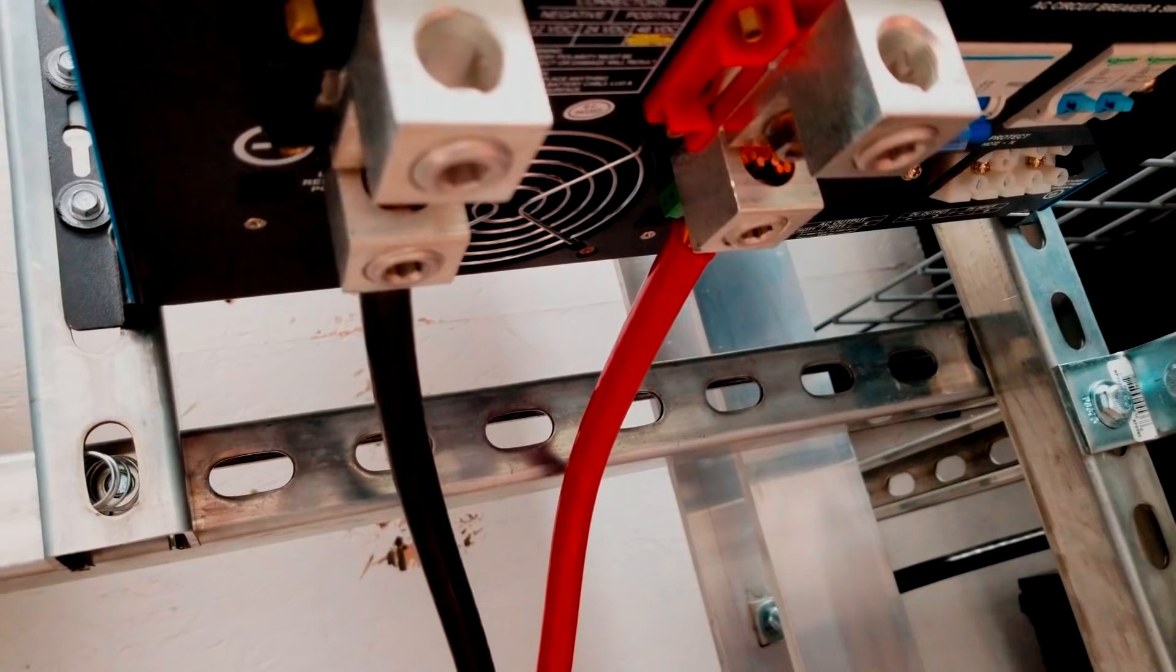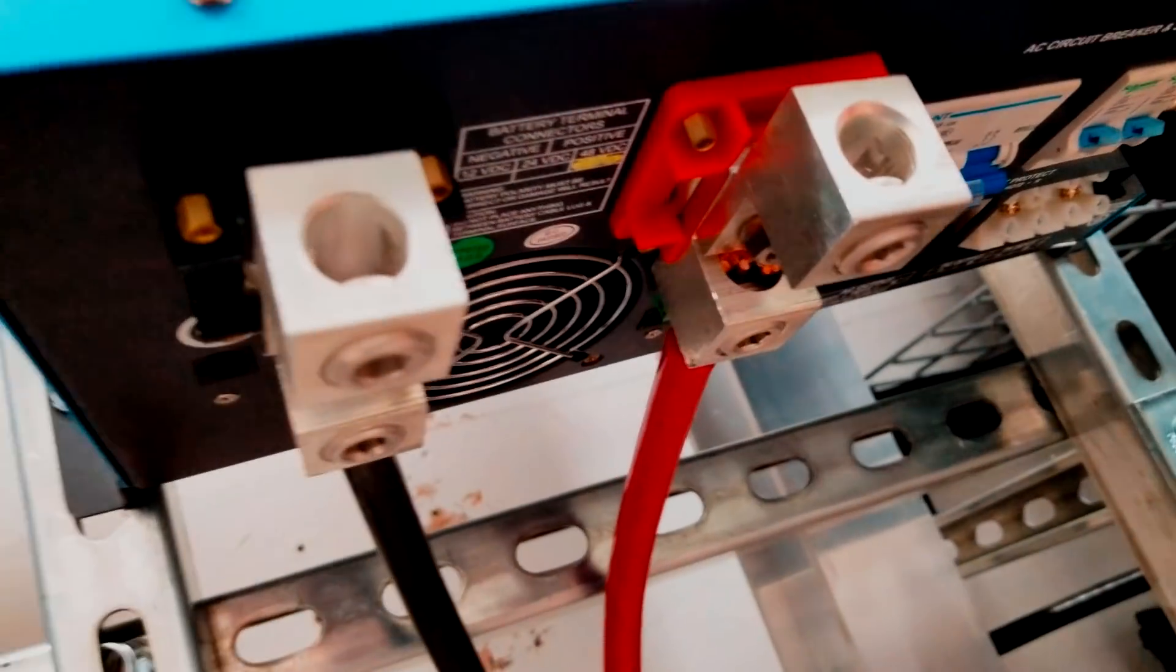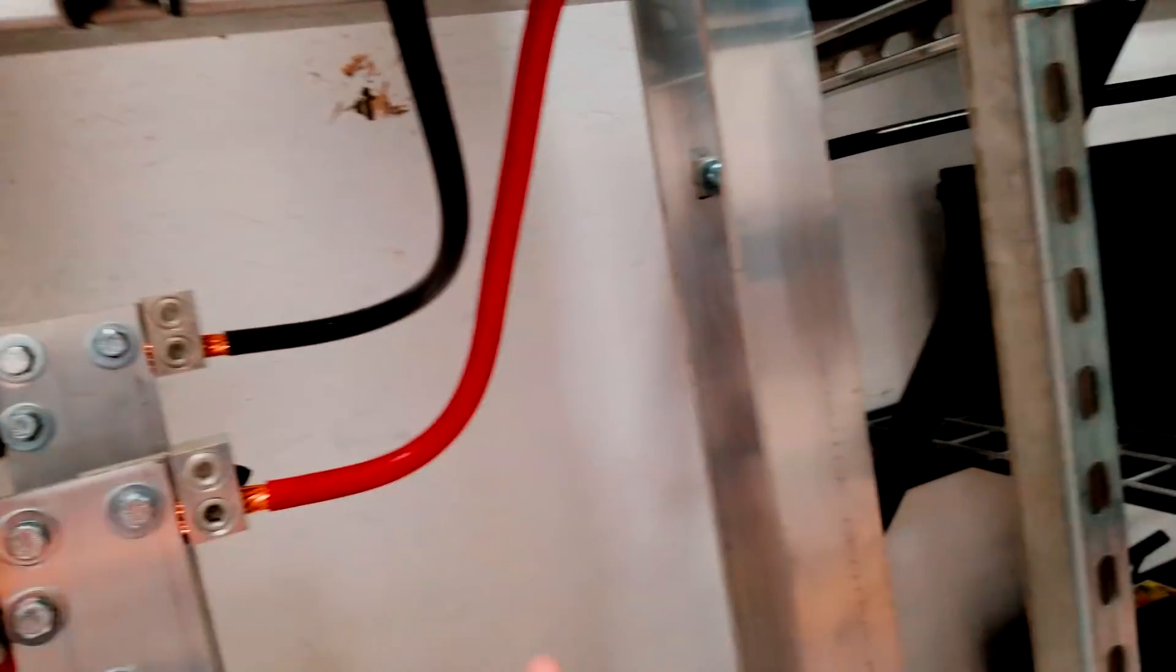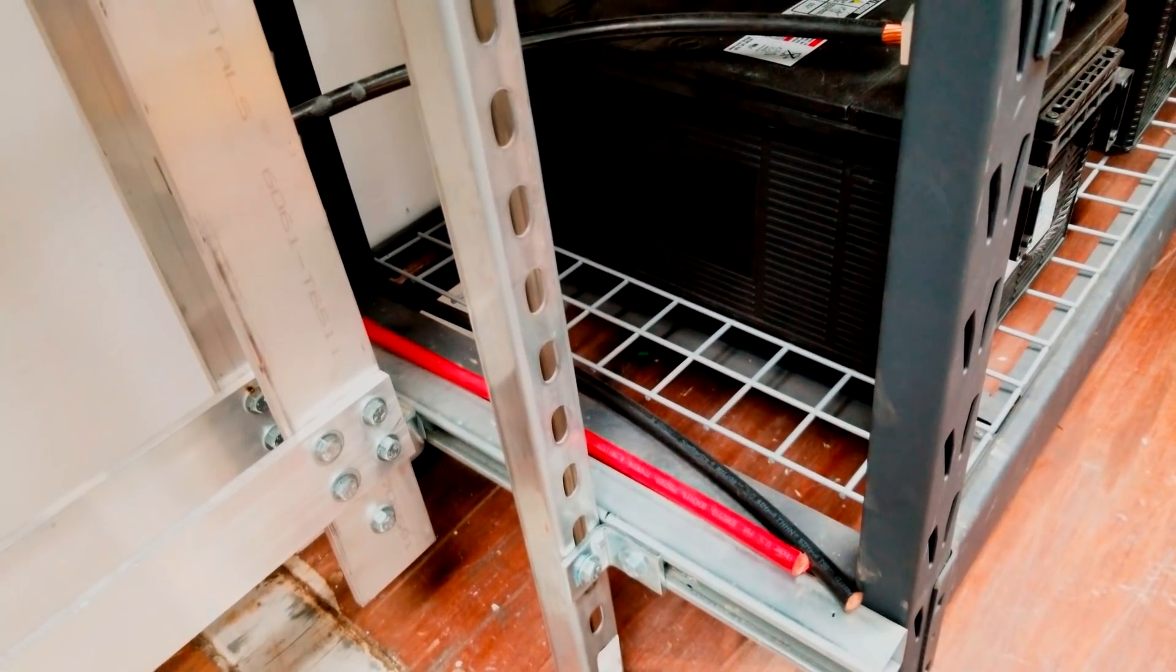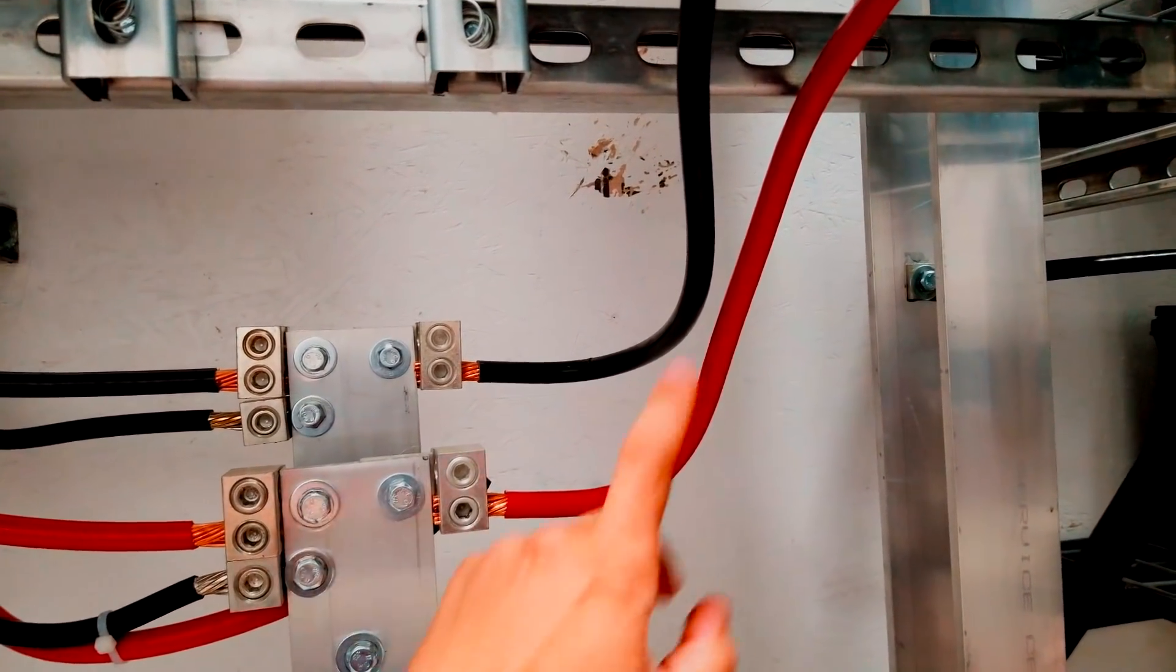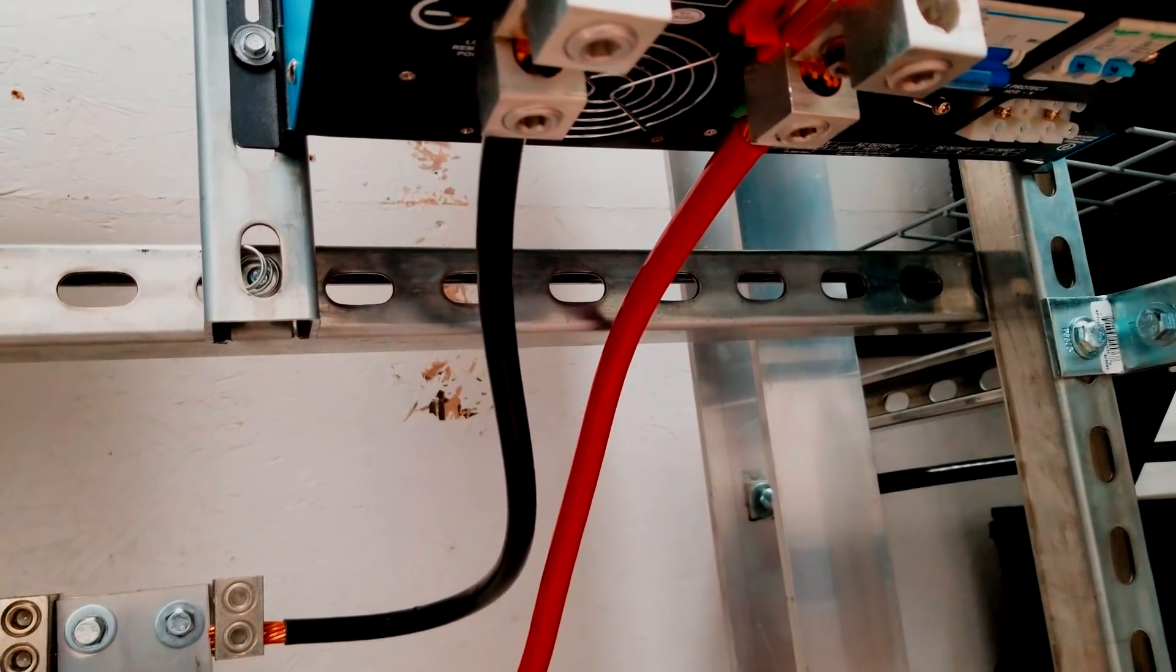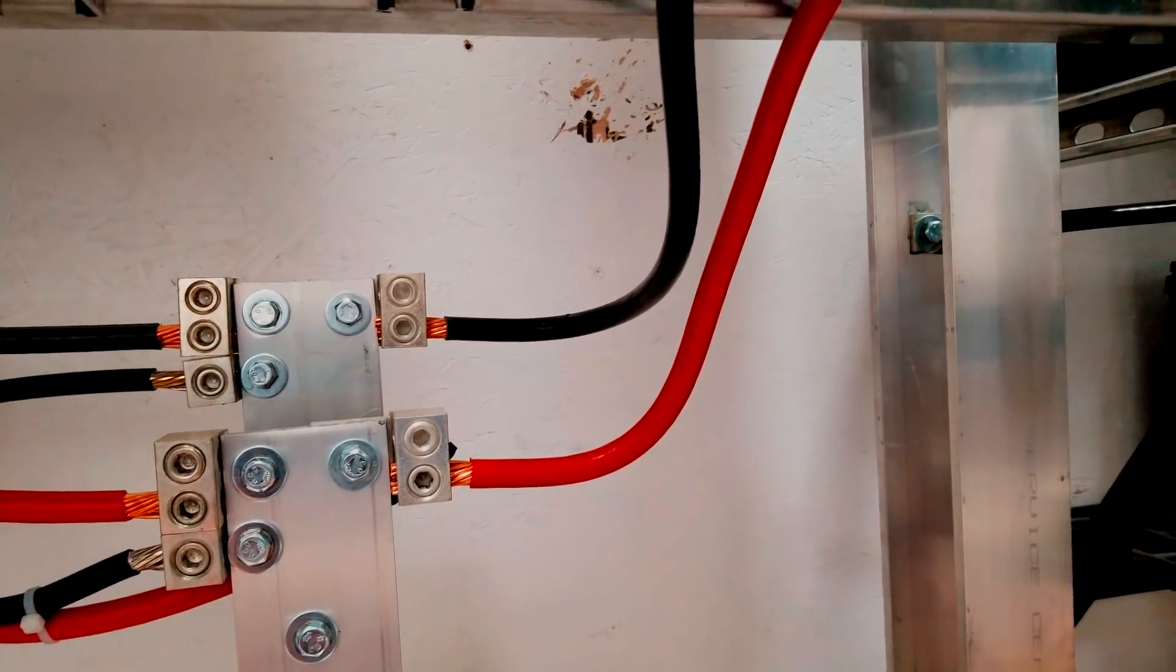Now I need to put these two barrel lugs up here on the inverter, because when I put these wires in, I measured them out and have the second parallel run of equal length set up, so that way the wire will be equivalent to a 400 amp capacity cable, but it'll be two parallel runs.